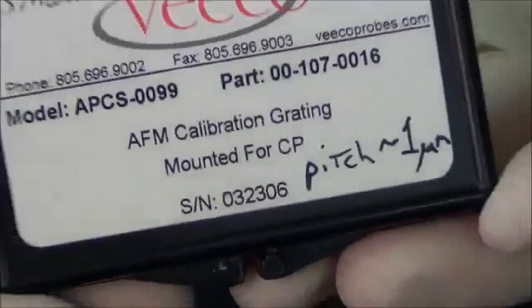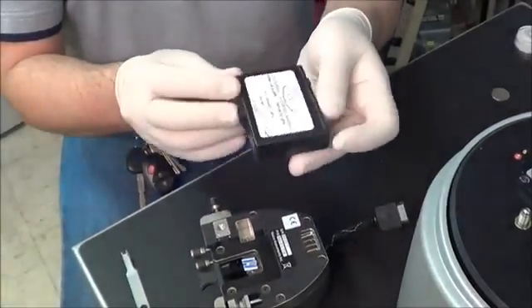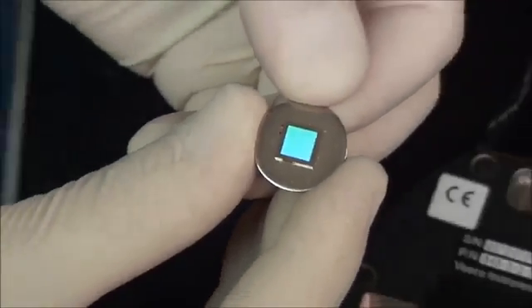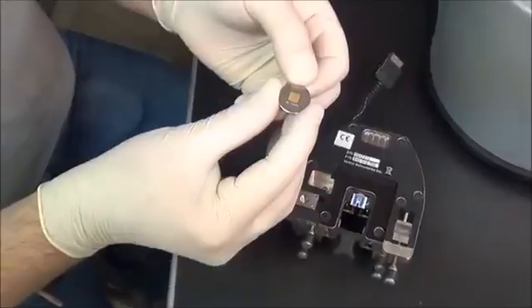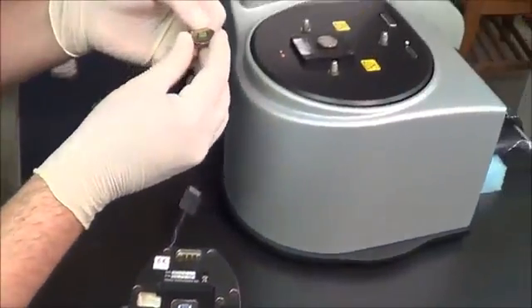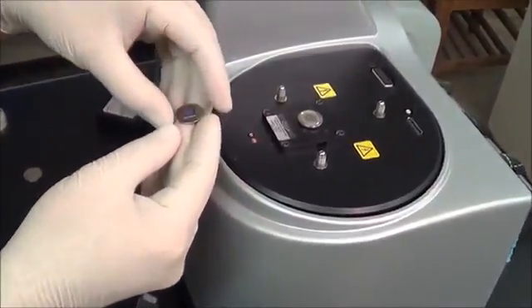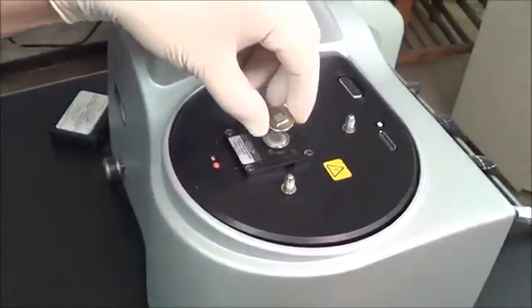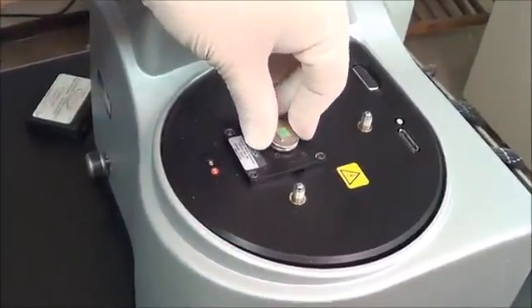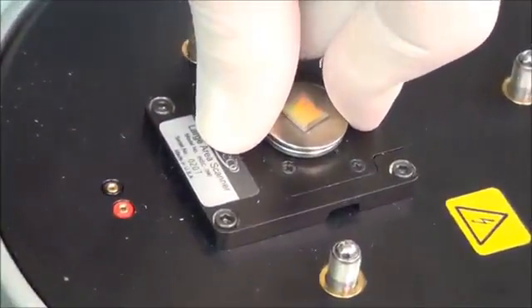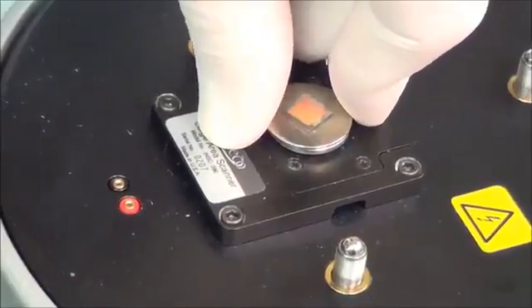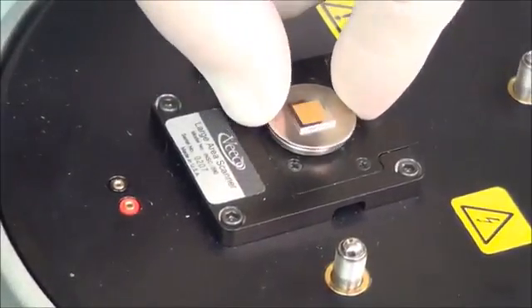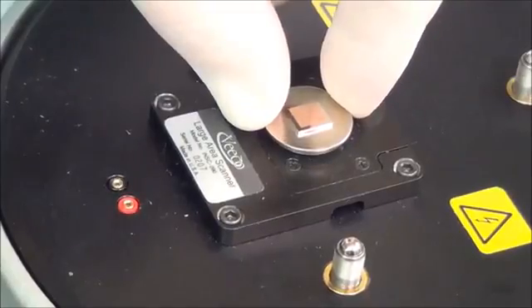To test that our AFM is working properly, we're going to use calibration grating with a pitch of 1 micron. When placing our sample onto the stage, it is held in place by magnets. Be careful not to let the force of the magnets slam the sample onto the stage, as this can damage our piezoelectric motors. Note that we rotate the sample to align with the stage. This ensures that our scan of the grating is even.